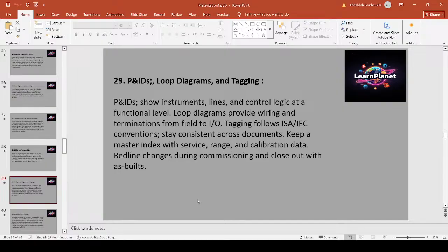P&IDs, loop diagrams, and tagging. P&IDs show instruments, lines, and control logic at a functional level. Loop diagrams provide wiring and terminations from field to I/O. For tagging, follow ISA and IEC conventions, stay consistent across documents, keep a master index with service, range, and calibration data, redline changes during commissioning, and close out with as-built.